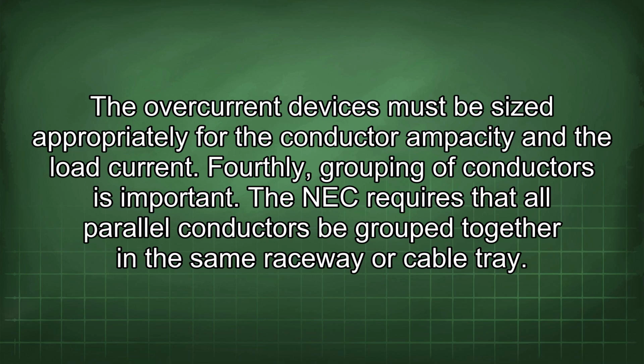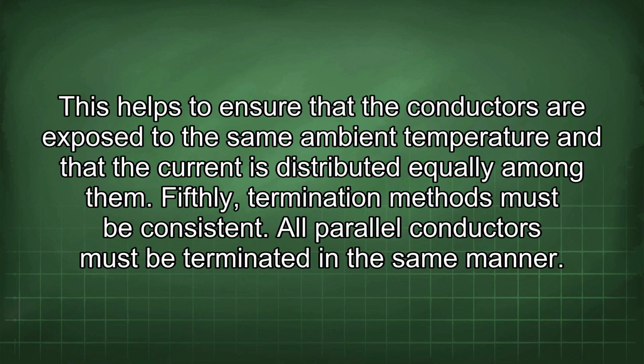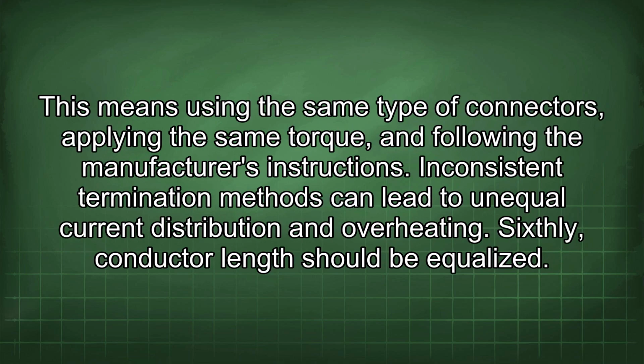Fourthly, grouping of conductors is important. The NEC requires that all parallel conductors be grouped together in the same raceway or cable tray. This helps to ensure that the conductors are exposed to the same ambient temperature and that the current is distributed equally among them. Fifthly, termination methods must be consistent. All parallel conductors must be terminated in the same manner. This means using the same type of connectors, applying the same torque, and following the manufacturer's instructions. Inconsistent termination methods can lead to unequal current distribution and overheating.